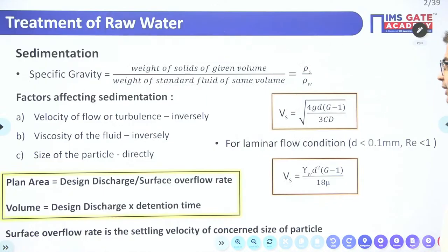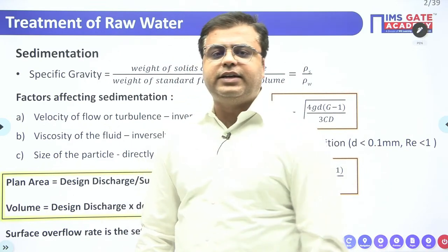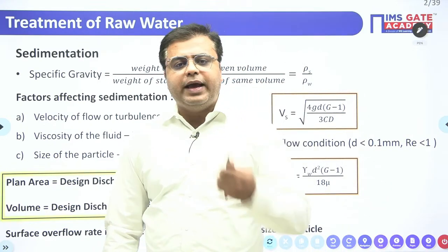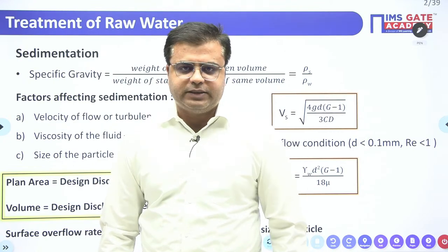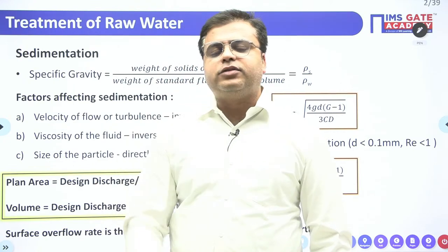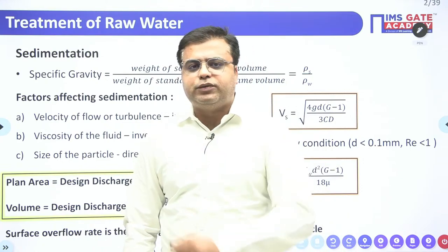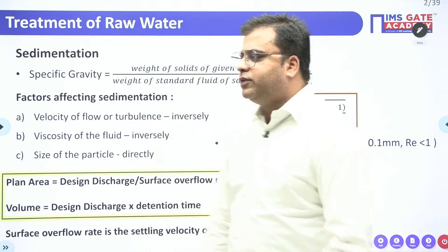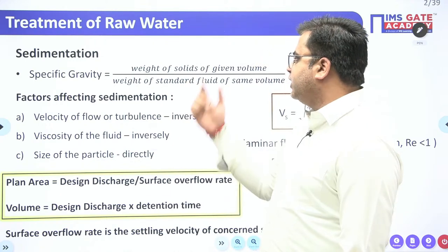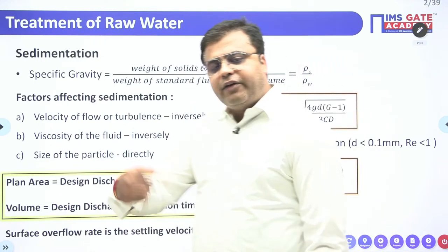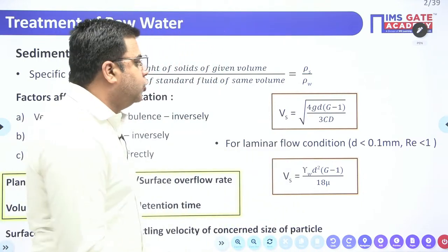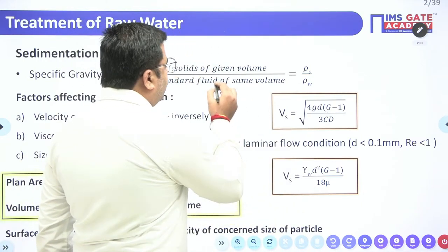Now, moving on, the next treatment technique is known as sedimentation. My dear students, sedimentation is a technique which is used to remove any kind of suspended solids which are present, right? The entire theory of sedimentation depends on a single parameter, which is known as the specific gravity. As you know, specific gravity is defined as the weight of the solid of given volume divided by the weight of the standard fluid of same volume. Usually we take this standard fluid as water.